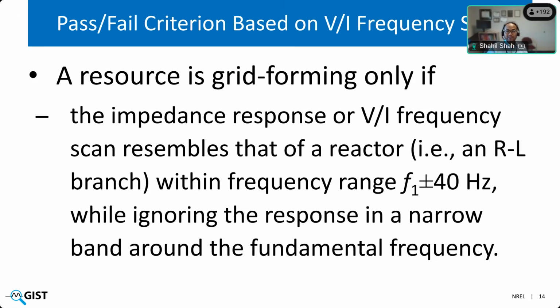The pass-fail criterion based on the V by I frequency scan is slightly different. In addition to active power response and reactive power response, the third way to check the voltage source behavior is to look at the equivalent Thevenin impedance of a resource or of a grid forming resource. If that resource is indeed behaving like a voltage source behind a reactor within a particular frequency range, in that frequency range its equivalent Thevenin impedance would be that of a reactor, because an ideal voltage source has no impedance.